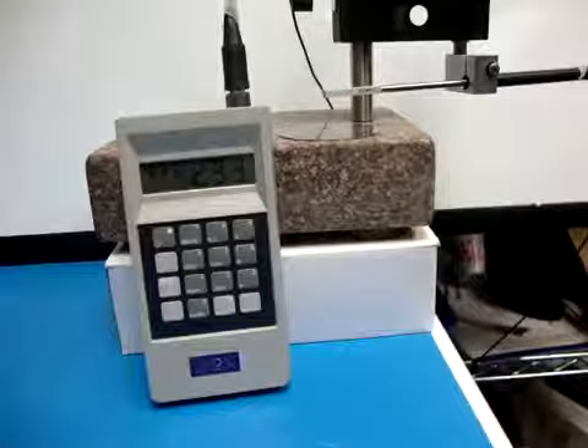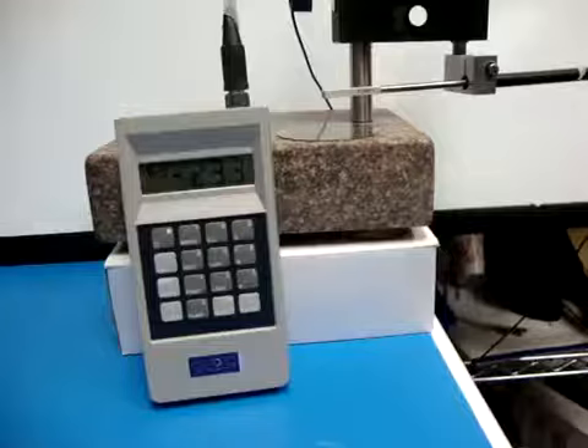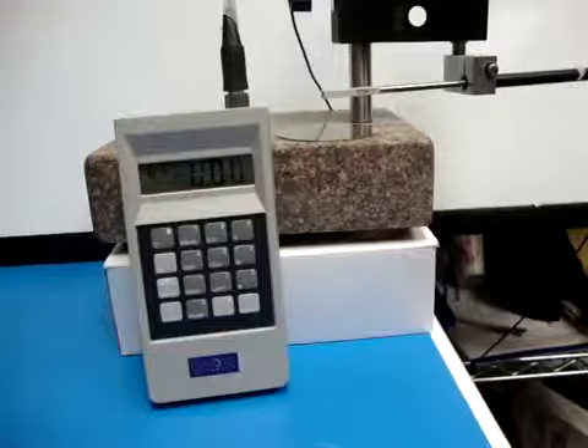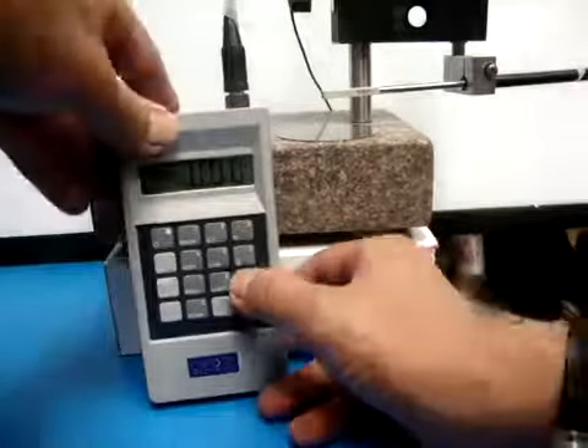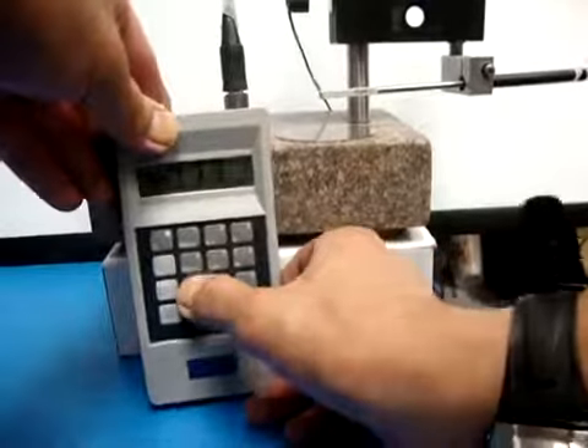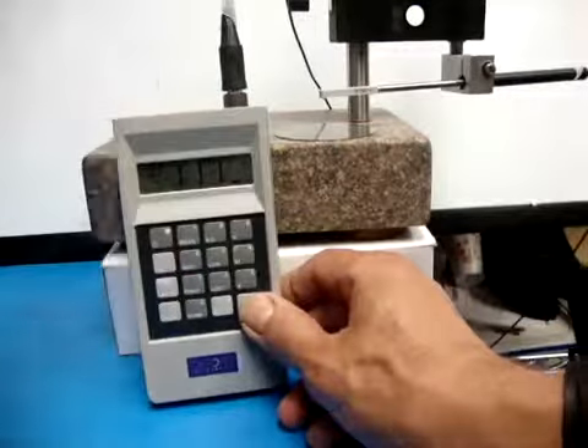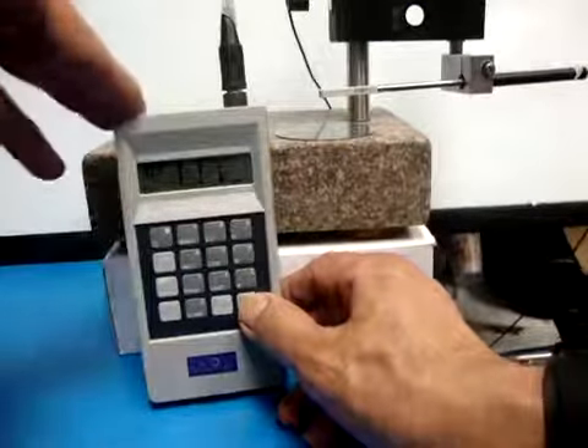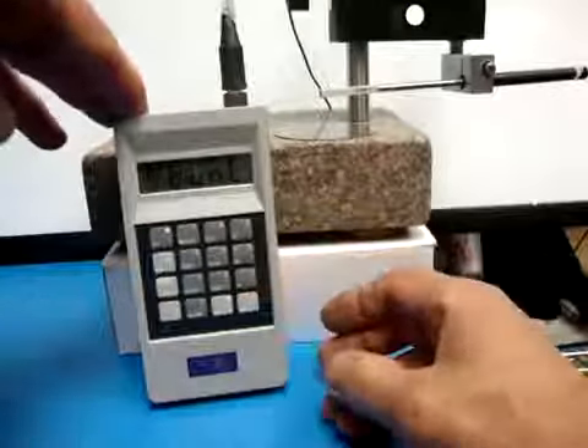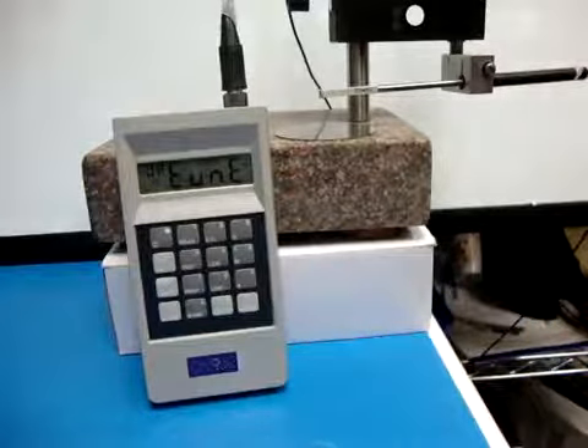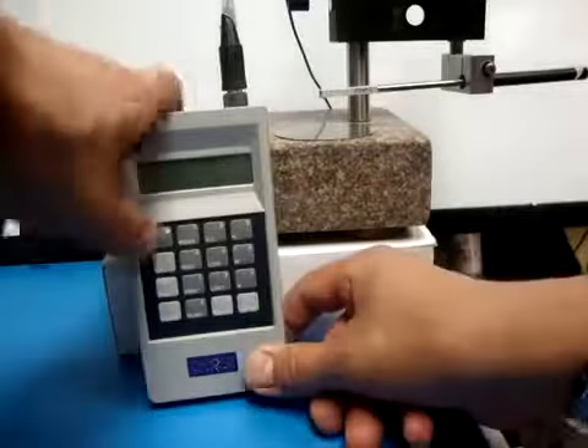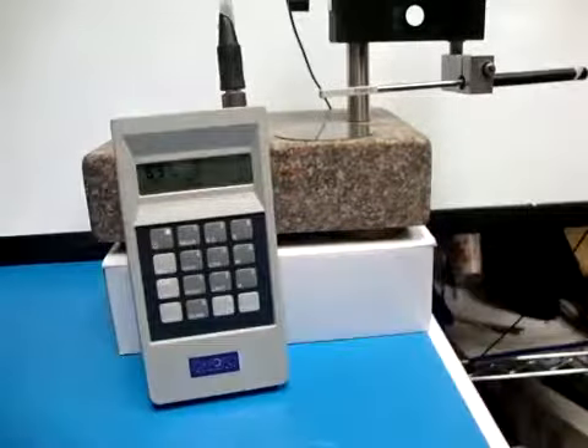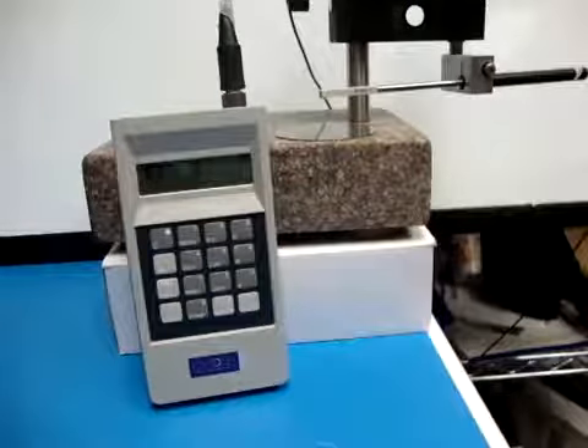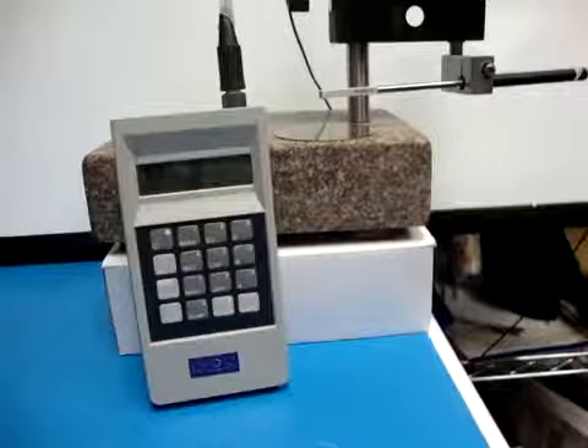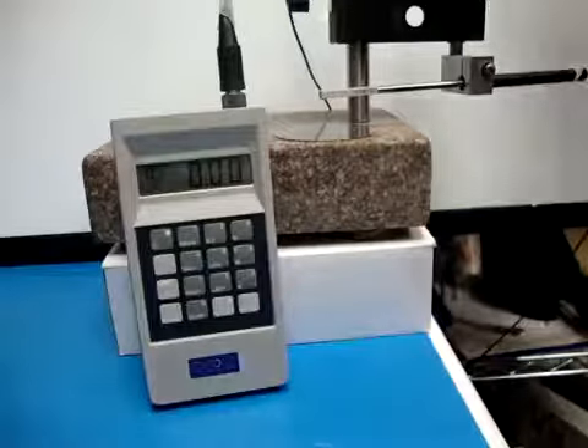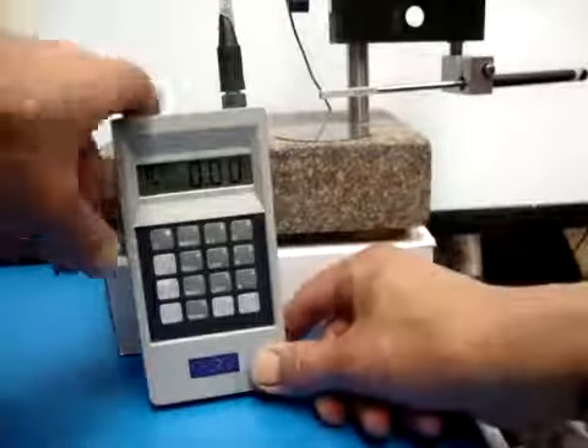And now, since every probe has a different offset, the next thing you have to do is tune out the offset for the probe. So you're going to want to do a star 111 and then hit, I hope that's readable, enter. And now it's tuning out the offset for this individual probe. Once we do that, we power back up, wait for the gauge to go through its sequence of logic, and we're going to cal out the base.